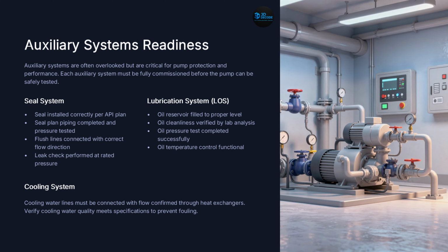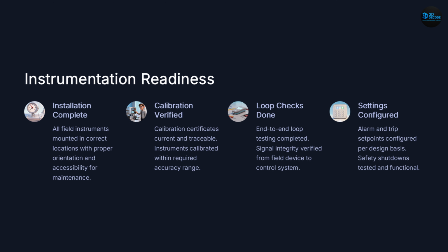Cooling water flow must be confirmed. Heat exchangers must be functional. Water quality must meet requirements, because overheating problems don't care how expensive the pump is. Without healthy auxiliary systems, reliable operation becomes impossible. Next, instrumentation readiness.